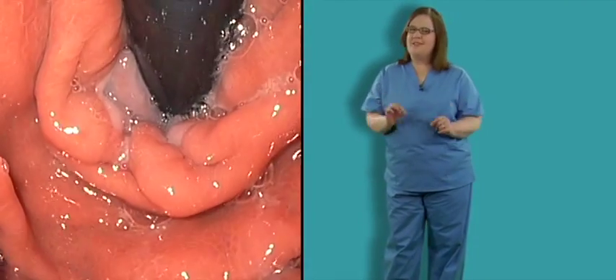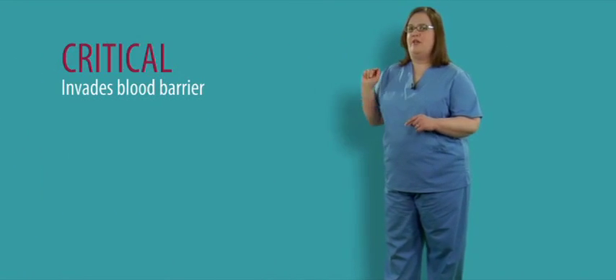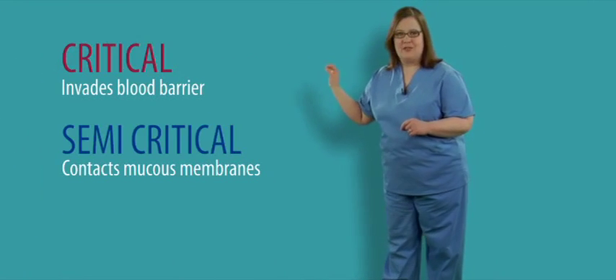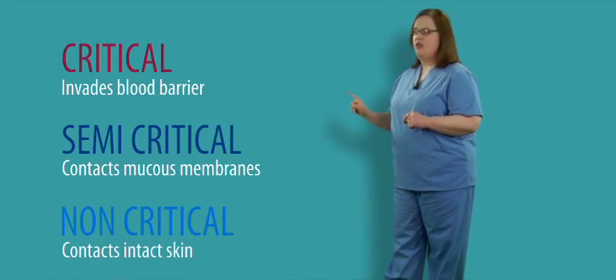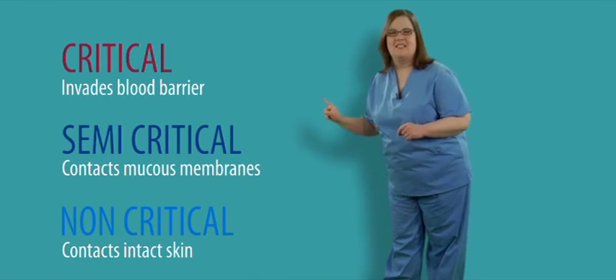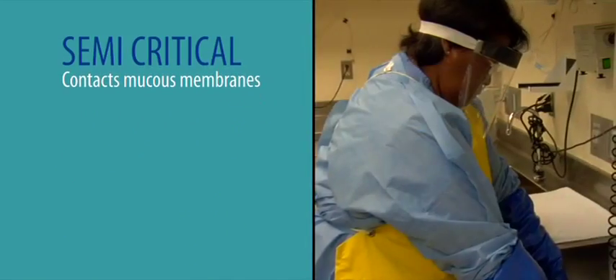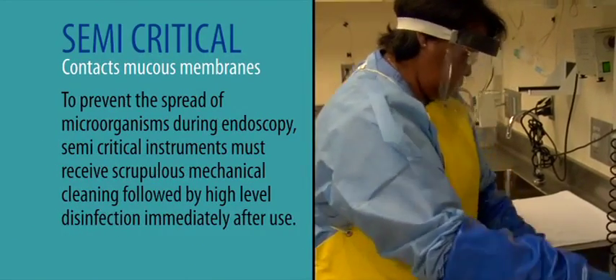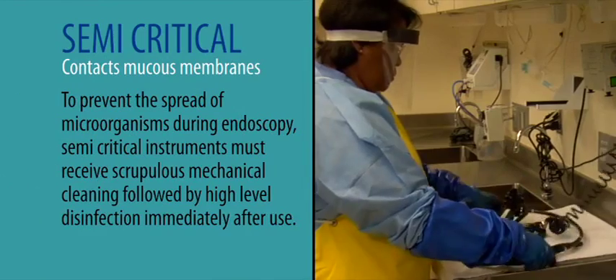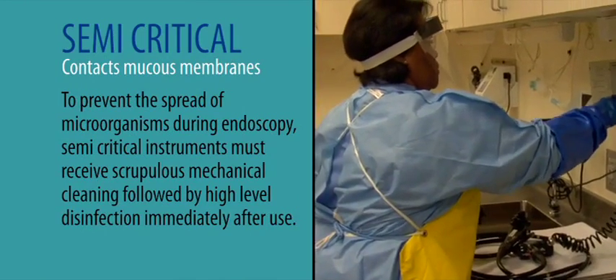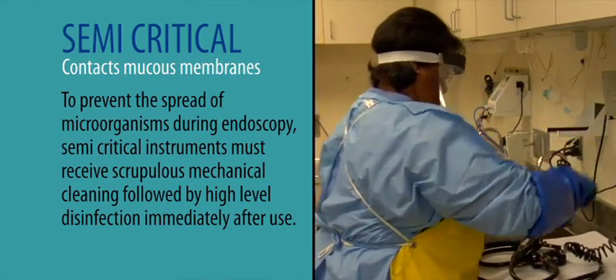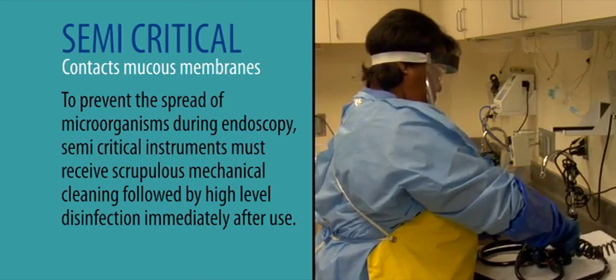Flexible endoscopes normally only come in contact with mucous membranes and are therefore considered semi-critical medical devices, according to the Centers for Disease Control classification. Critical invades the blood barrier, semi-critical contacts mucous membranes, and non-critical contacts intact skin.